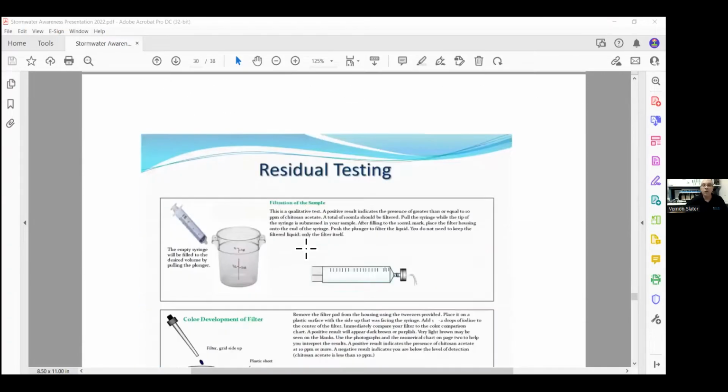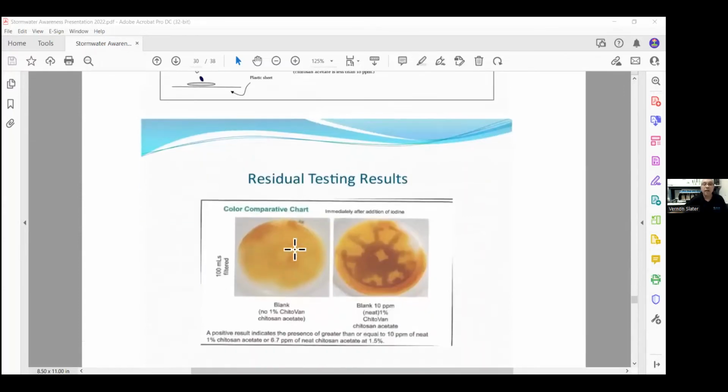With chemicals used in stormwater treatment, how do you guarantee no chemicals into the environment? And I am going to share screen again. We use the residual test. It's essentially a starch iodine test where we have, this would be the filter of what it would look like without any Chitosan, and this shows the presence. It does not determine concentration. This just tells me, is it present or is it not? And with that known, that it comes out like this, we can keep discharging. We check this about every 4 hours as a company. It's required every 8 hours by the permit.